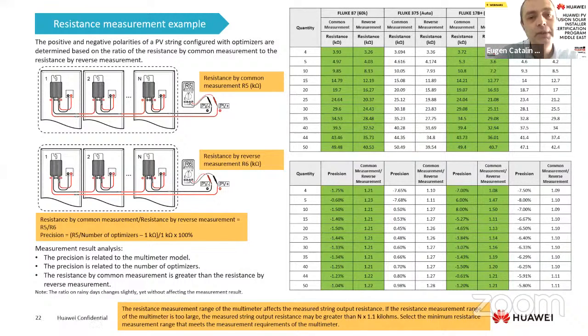And I need to check my string to see if I installed it correctly and if the polarity on the string is correct. So first, I will do a correct measurement. What does this mean? Plus to plus, minus to minus. And I will have this value, 9.85. So this means that the string is installed correctly. But now I also need to check the polarity.